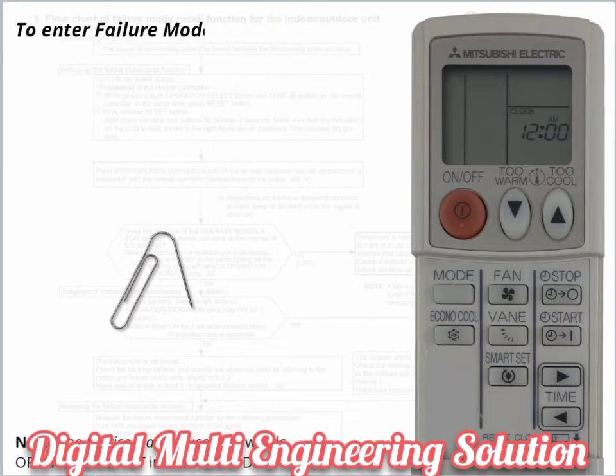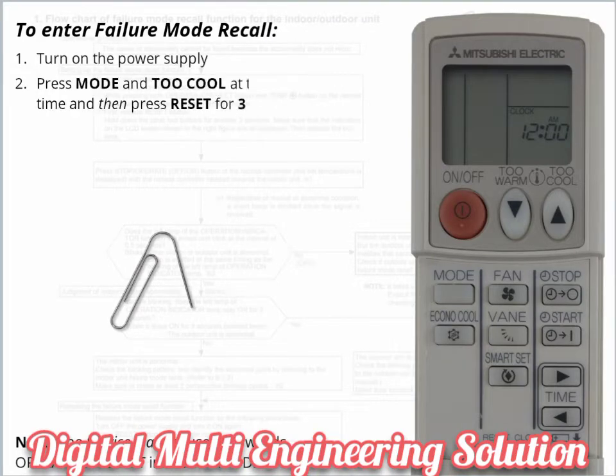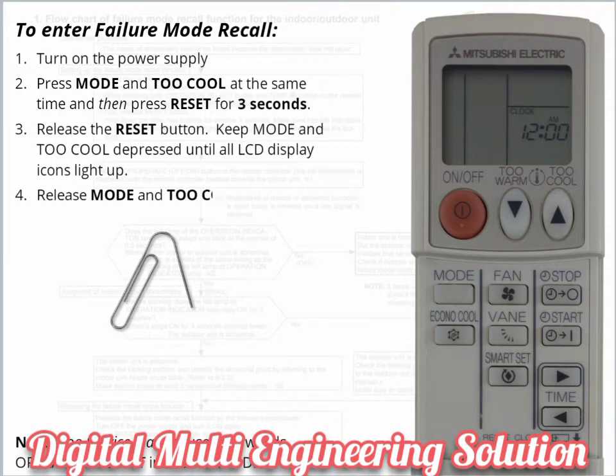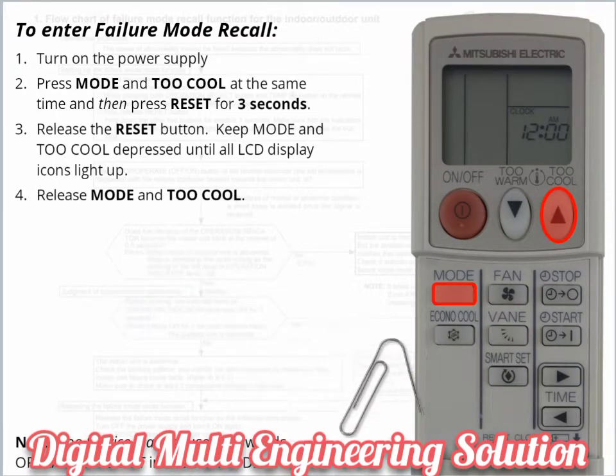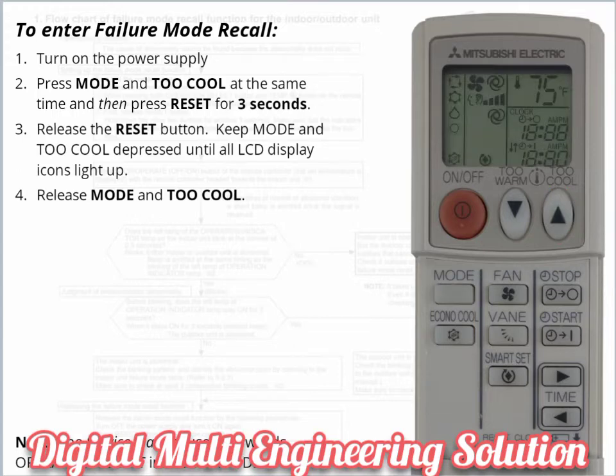To enter Failure Mode Recall, turn on the power supply. Press Mode and Too Cool at the same time and then press Reset for 3 seconds. Release the Reset button, but keep Mode and Too Cool depressed until all LCD display icons light up. Once they display, release Mode and Too Cool.